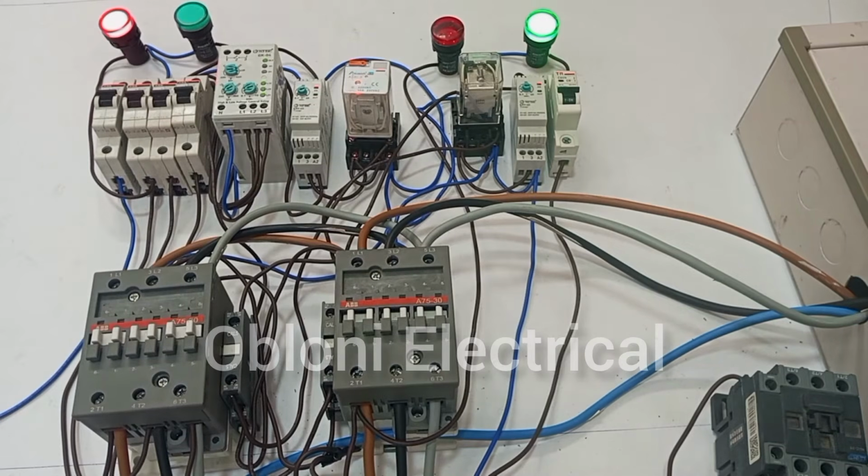There are different ways of doing that arrangement. But what I'm going to do here is one of the best ways that you can wire your automatic changeover switch to your generator. In that case, on your generator, you will need an automatic start controller. And on that automatic start controller, we have two contacts that should close for the generator to start. So right now, we are going to extend those connections through a wire like this.